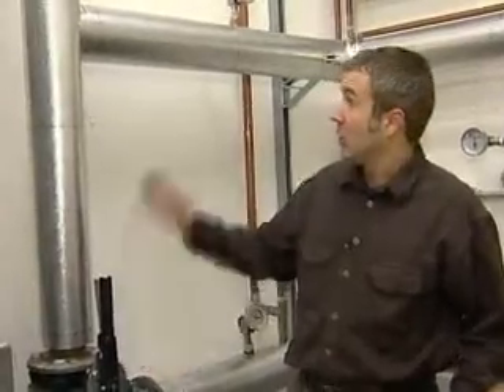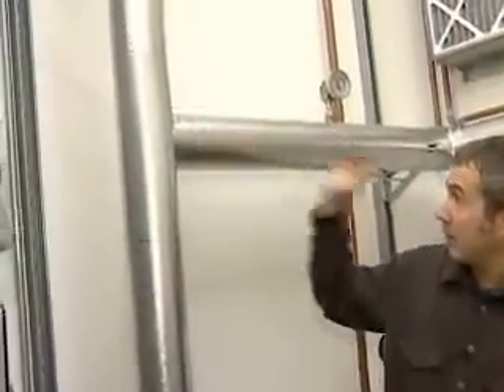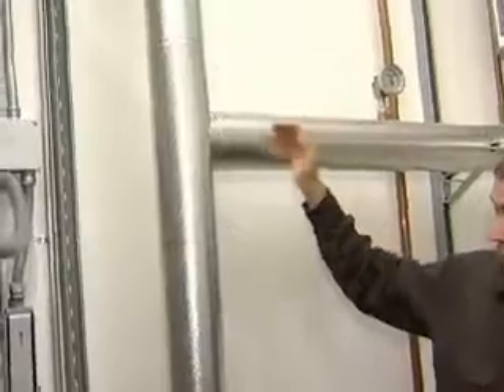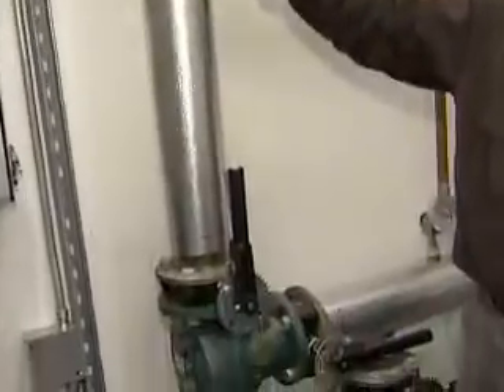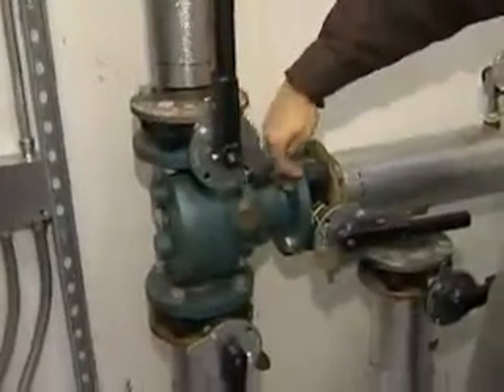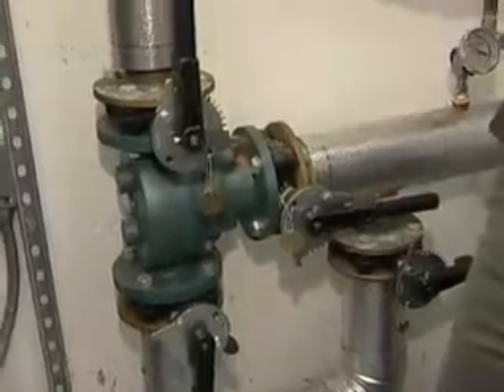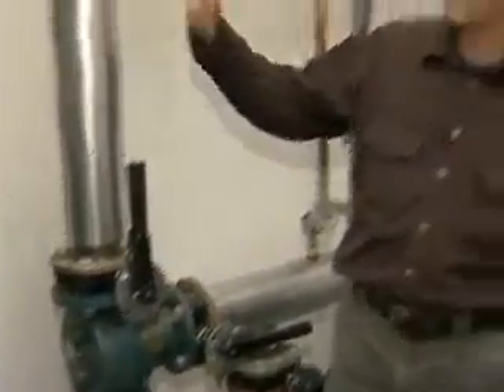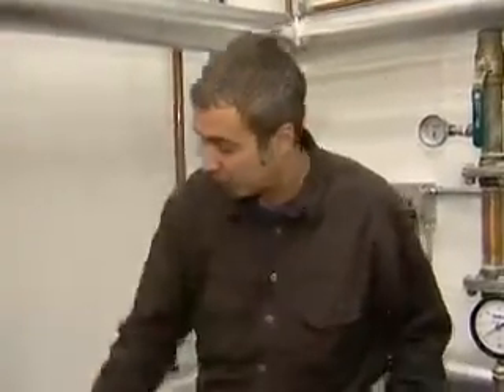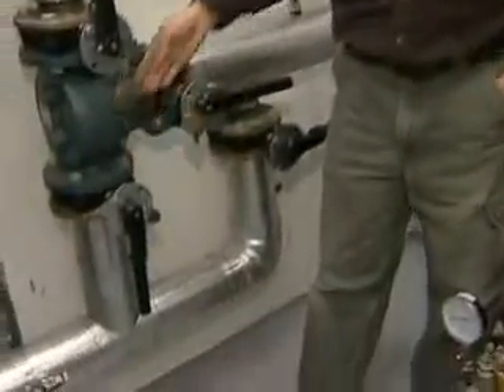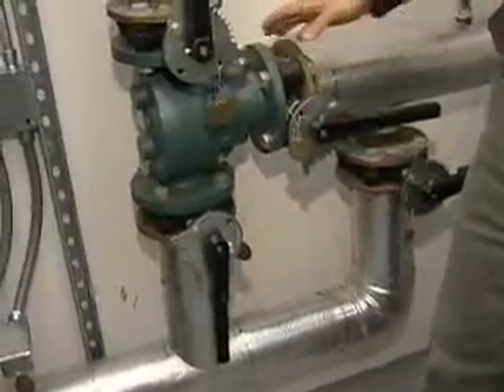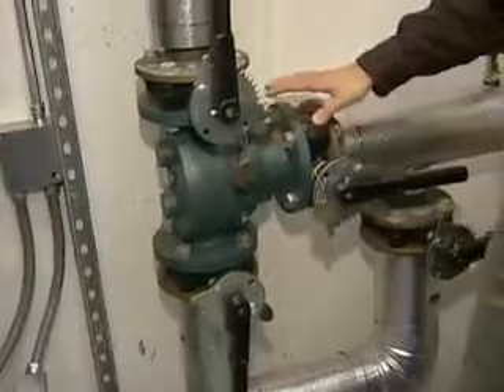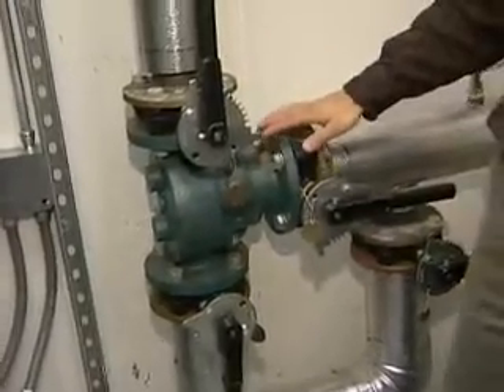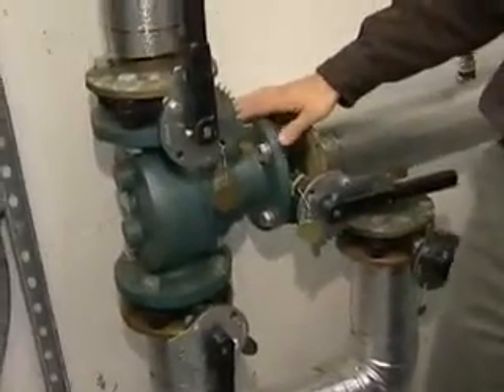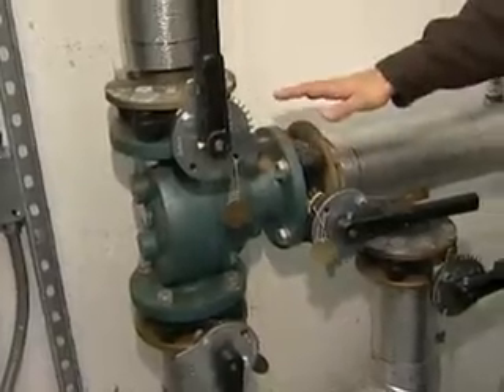to the engine. So the hot coolant coming from the engines, if we're using enough waste heat to keep the system down to temperature, it'll come straight through the valve, go right back to the engines. As the temperature begins to climb, it'll divert coolant through the radiators, come back through the opposite port, and then go back to the engine. So this is a device that just operates on its own. There's no control function required. There's no maintenance really required on it. It just sits there and operates.